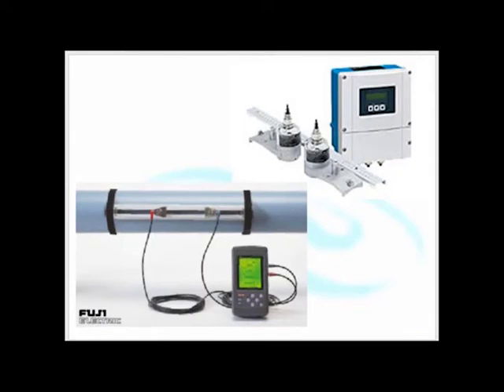There's one proviso. If here's your pipe, if you have air bubbles in the top and slurry in the bottom, you have to make sure that you don't put your ultrasonic sensor at the top or the bottom, because the air bubbles and the slurry will kill the sound.